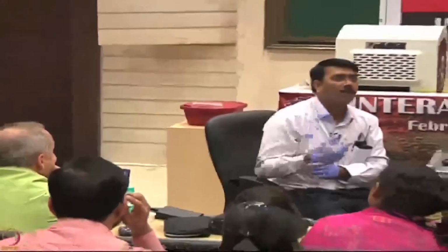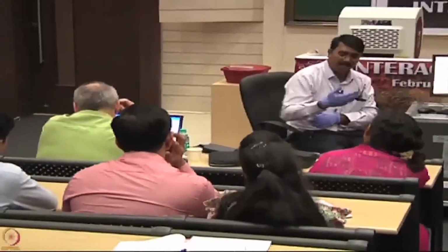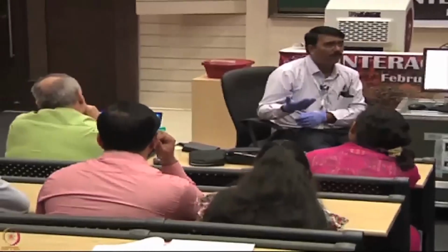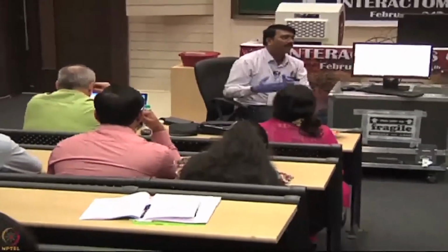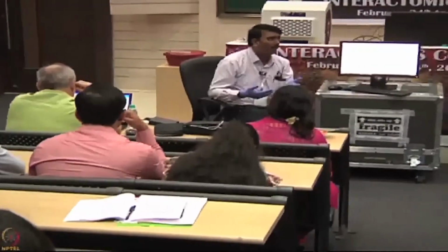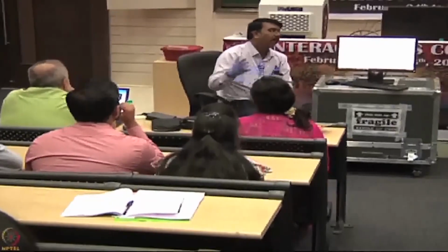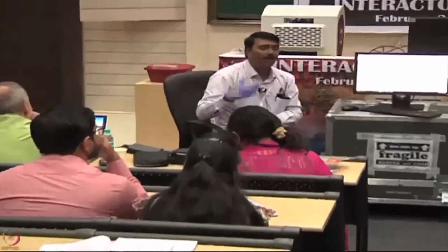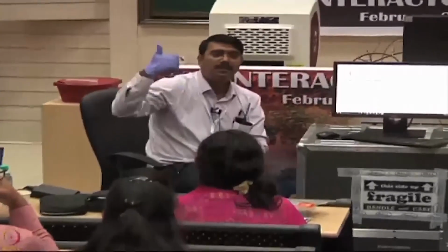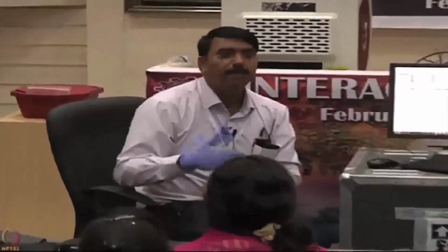That's why there is a step called regeneration. The remaining 90% is still bound to your sensor surface. Using agents like high salt strength solutions, like 1 molar or 2 molar sodium chloride or magnesium chloride, or if you want to change the pH, like 10 millimolar glycine at pH 2 or pH 1.5, that's good enough. Or we will go with a 50 millimolar sodium hydroxide solution. That will remove the remaining bound analyte. One thing we have to consider when doing regeneration is the stability of your ligand. Whatever you immobilized on the sensor surface should be stable after the regeneration. Sometimes, if you use conditions like glycine or a higher pH, your protein undergoes denaturation, and then in the next experiment we can't use the sensor again. That's why we have to carefully consider the regeneration solutions.